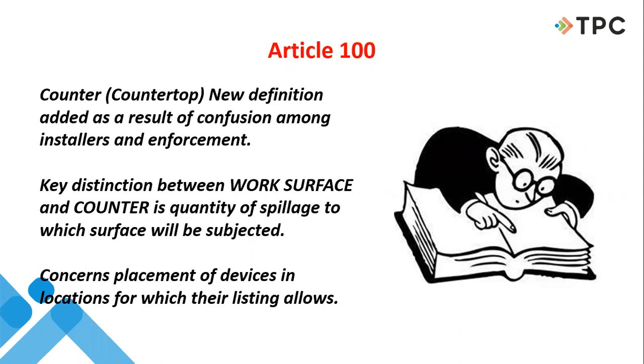Basically, what we're striving for is we needed to clarify concerns for certain types of receptacles, devices in general, that get mounted in countertops. Well, the listing, the design, the approval of certain types, certain styles of devices relies on, as we're mentioning here, the type of surface, the type of location where these things are installed.